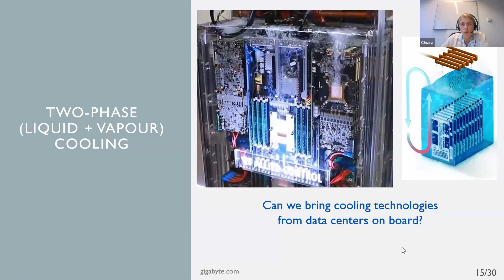We know that two-phase flow cooling has the advantage of very high heat removal capacity, thanks to the latent heat combined with convection of the liquid. So it tends to be more efficient, and allows us to shrink the size of the cooling components.